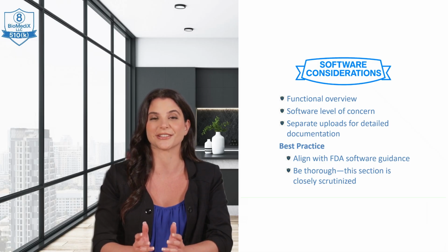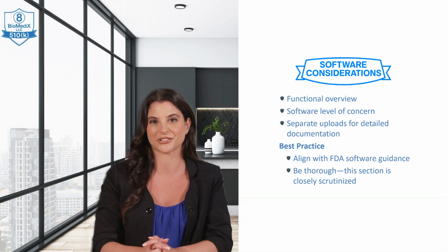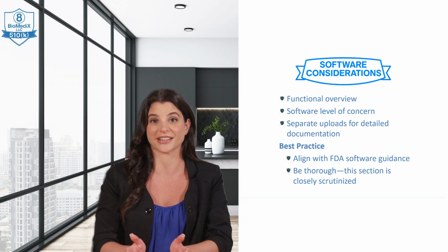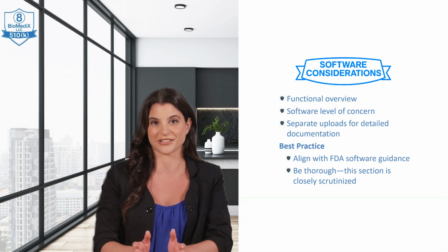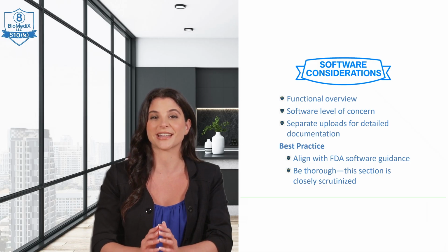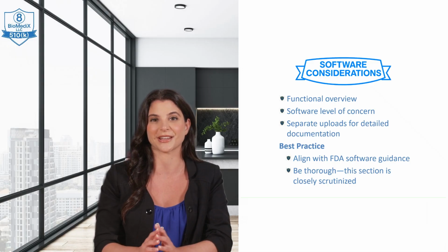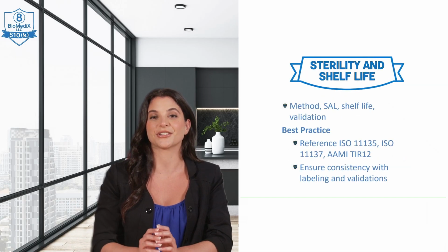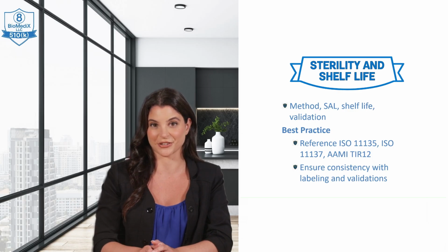For software description, if applicable, if your device includes software, eSTAR has dedicated prompts for high-level software function and architecture, software level of concern, and links to more detailed documentation. This includes the software description document, hazard analysis, software requirement specification, architectural design, and others, which are uploaded separately. The best practice is to align your software documentation with the FDA's guidance for the content of pre-market submissions for software contained in medical devices. Be thorough, as software is a common area for reviewer questions.